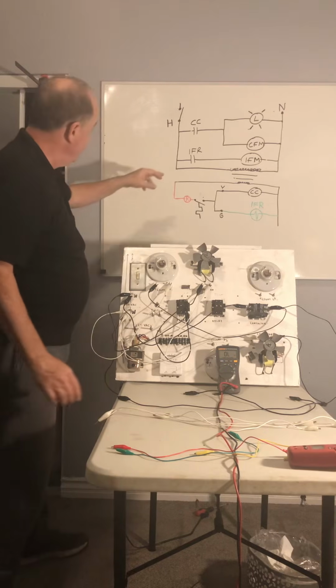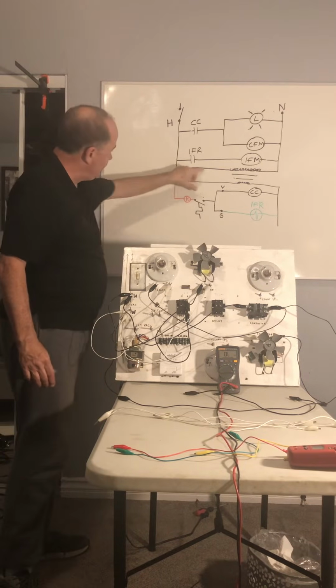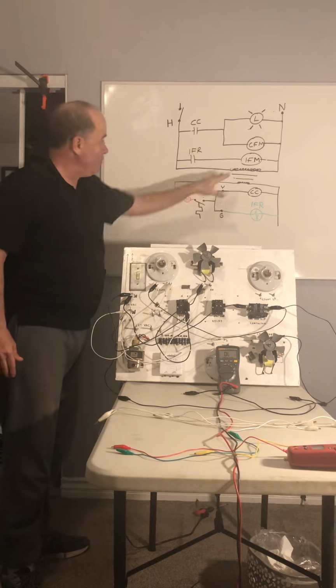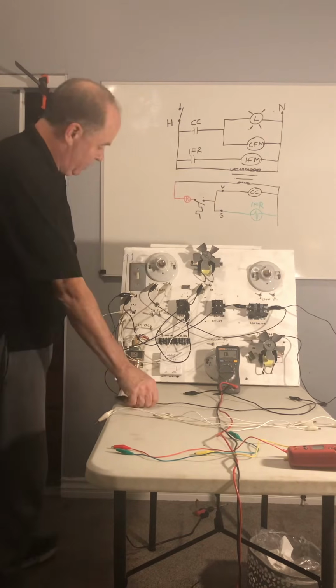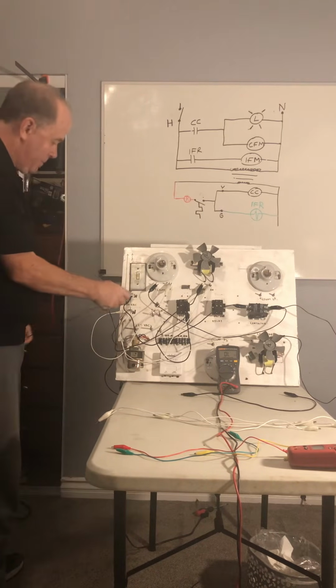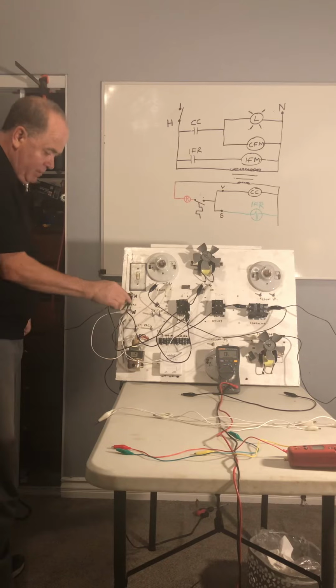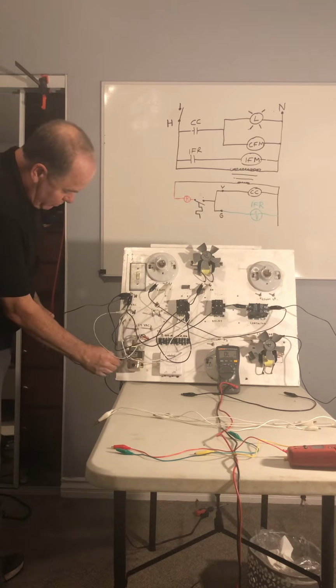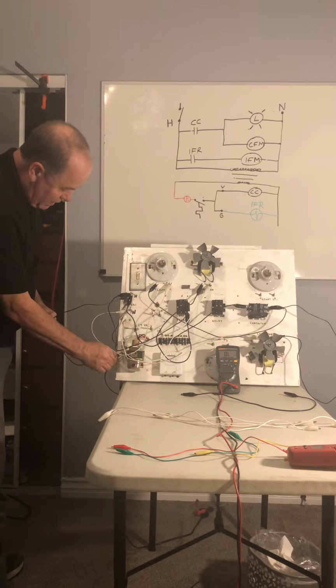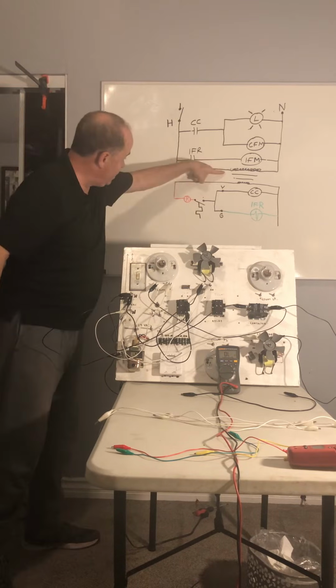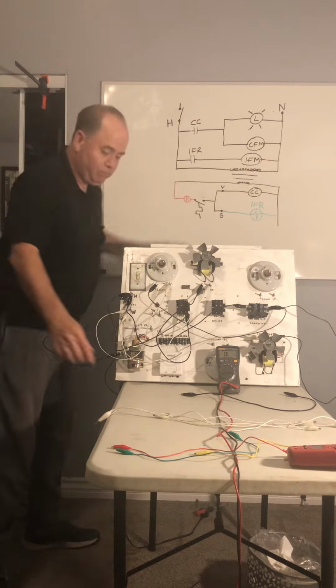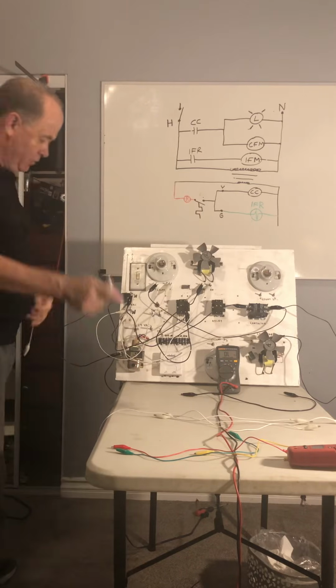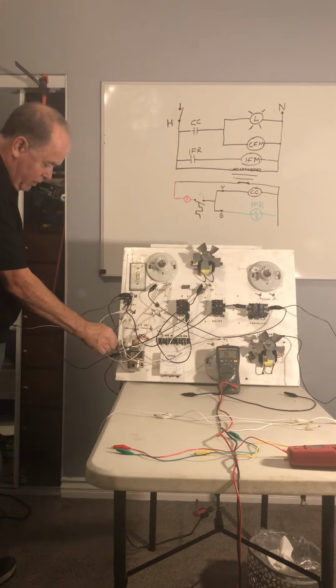And now we have one more thing: this wire coming down here to power up the transformer, the primary of the transformer. So we need one more hot, and we need to come into the primary of the transformer here. And we wire up the primary side here, and then back to neutral off of the other side of the primary of the transformer.